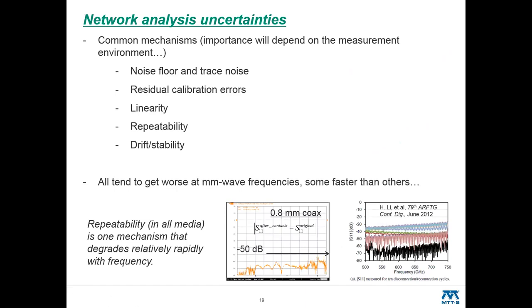If we sort of throw all these things together and try to get a bigger picture of overall uncertainties, here are some of the common mechanisms. Noise floor and trace noise, although we didn't talk about it too much here, don't tend to get worse that rapidly as we go higher in frequency. They do a bit, but the technologies are keeping pace, so those aren't degrading too fast. Residual calibration errors, how well do you know your standards, is really what that boils down to, and that isn't getting worse very dramatically either.